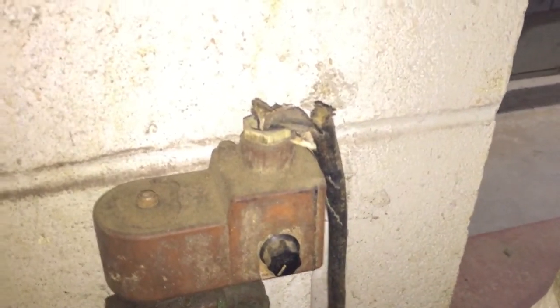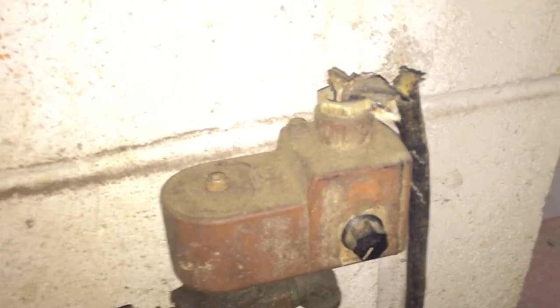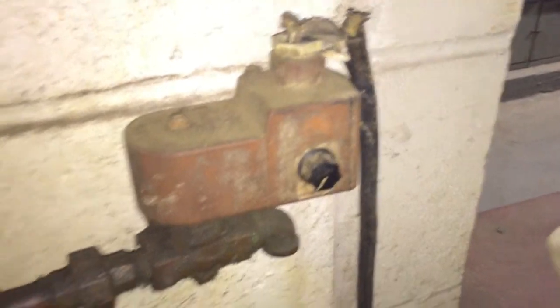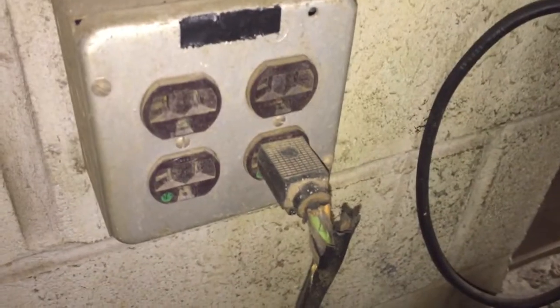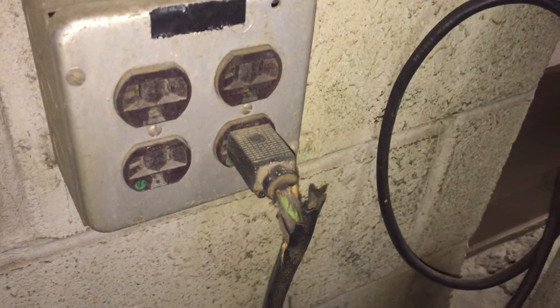So what we end up with is a couple of violations. One being section 400.12 number 7: a flexible cord is not permitted to be used subject to physical damage. This is clearly damaged. I don't know how it got damaged, but it is nonetheless damaged pretty badly.